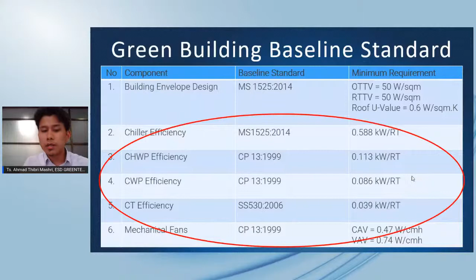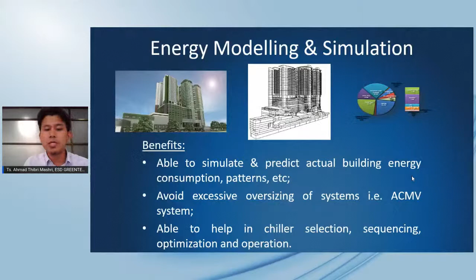Okay, and of course the idea of ensuring that the building, I mean the ACMV system, is operating efficiently at all load conditions can only be satisfied when we know the actual building load condition. Take for instance, energy modeling and simulation is one of the requirements in Green RE for higher level categories. So we are required to model the building before it's even constructed to predict how the building is going to operate. From this we can know the building load condition at all times, 365 days of the year, and use it for chiller selection, chiller sequencing, and also optimization and operation.